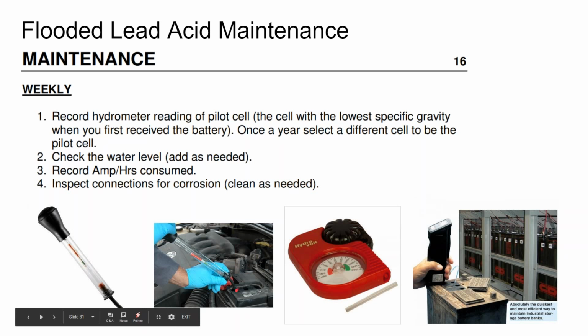You water your batteries and maintain your batteries when you're using them. In that winter period where you're really operating your batteries all the way down to their low end range because of lack of sunlight, this becomes a weekly task. Or in the summertime, with high air conditioning loads, you're cycling your battery more deeply, it's evaporating more water, and that's when this becomes a weekly task.